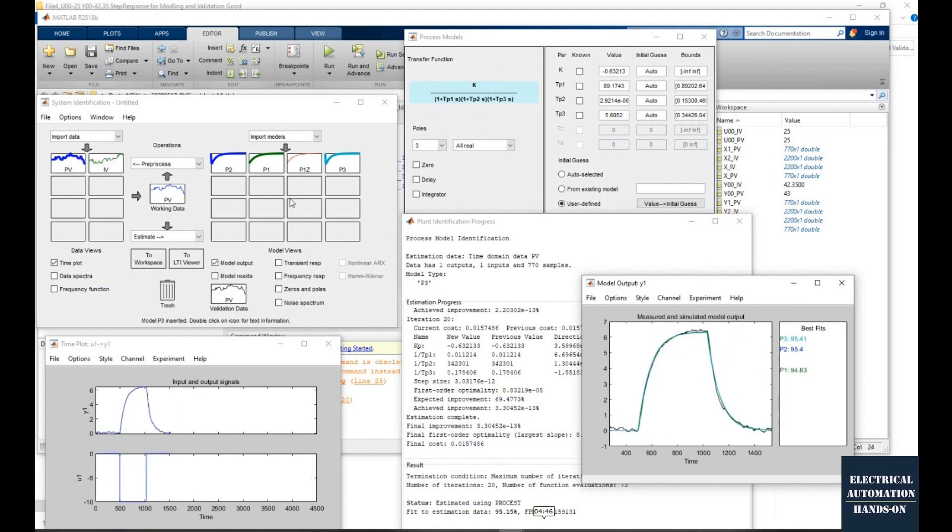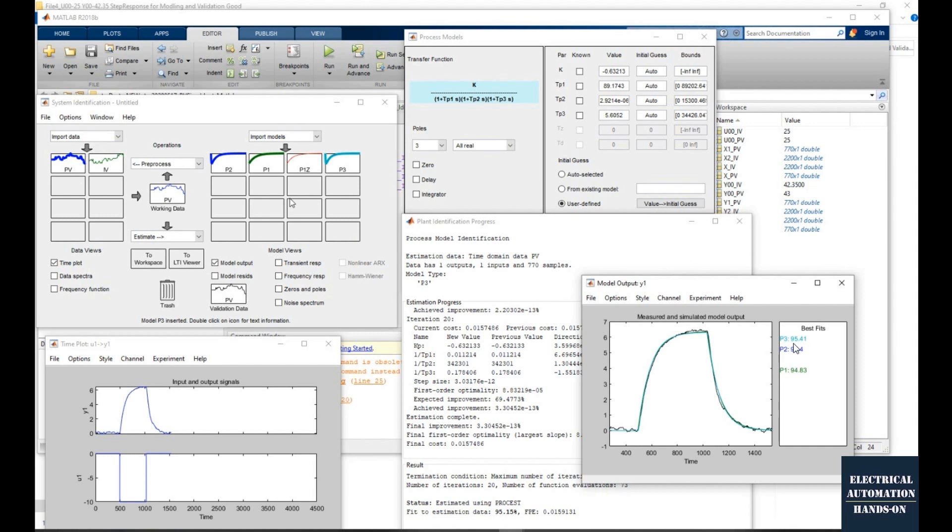After I tried different models, I tried a second order, first order, three orders, and even the model with a zero. So eventually I found the second order model that can give us the best fit. Here, 95%. So that's why eventually I selected this second order model as our process model.